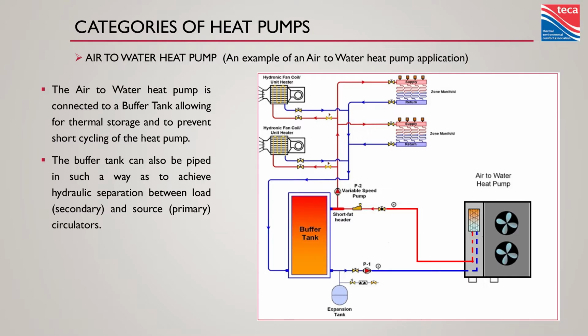We've got all kinds of different heat emitters in hydronics. Your big slabs full of concrete and what we call thermal mass. Thermal mass is all that energy we can charge into that slab and then just let release for a long period of time. Great for limiting cycling on a heat pump, but what if you're using panel radiators? What if you're using staple up underneath the joist space? What if you're using fan coils? Somebody turns up a thermostat because they want to be warm. You want the hot water coming out of that heat pump going straight to that fan coil right away.